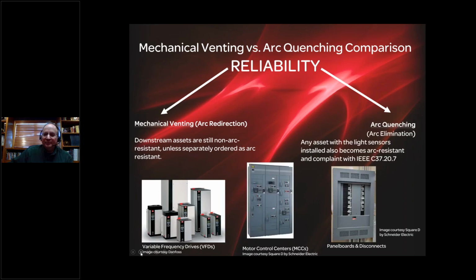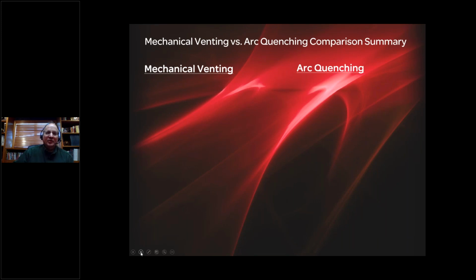Whereas with arc quenching, any asset with the light sensors installed is protected, and the light sensors are inexpensive. It's less than $120 for a light sensor. And each light sensor can protect up to 2 square meters of volume in a typical application. We can protect variable frequency drives, motor control centers, panel boards, and disconnects. So when we compare the two, mechanical venting only protects when the equipment is closed, arc quenching when it's open or closed.